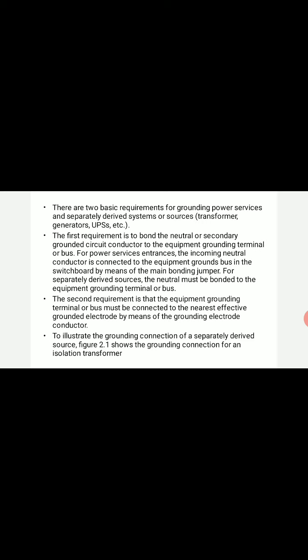There are two basic requirements for grounding power services. The first requirement is to bond the neutral or secondary grounded circuit conductor to the equipment grounding terminal or bus. For power service entrances, the incoming neutral conductor is connected to equipment grounds in the switchboard by means of a main bonding jumper. For separately derived sources, the neutral must be bonded to the equipment grounding terminal or bus.